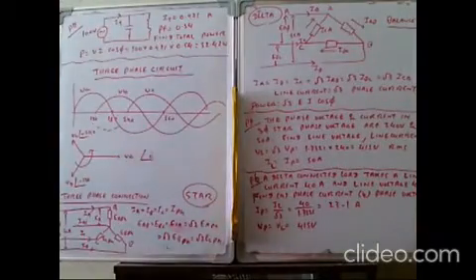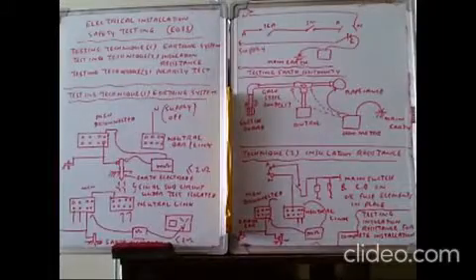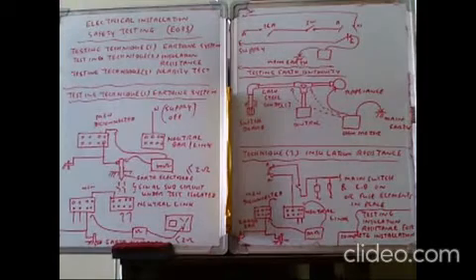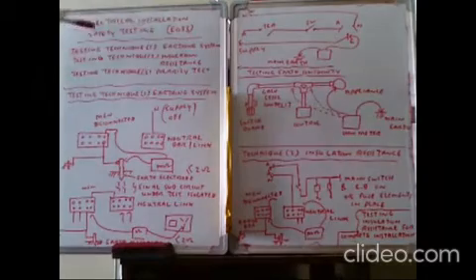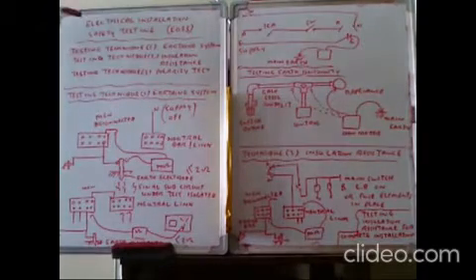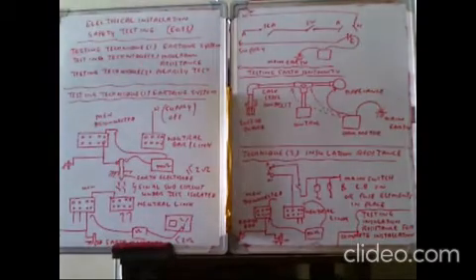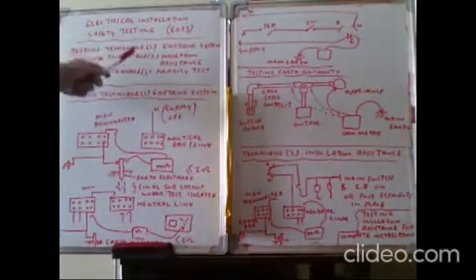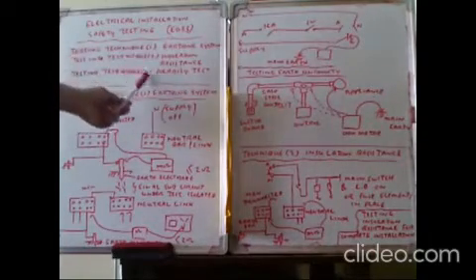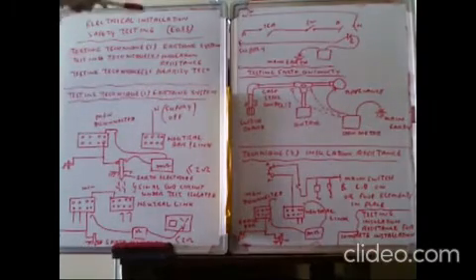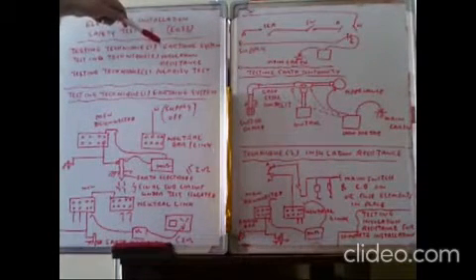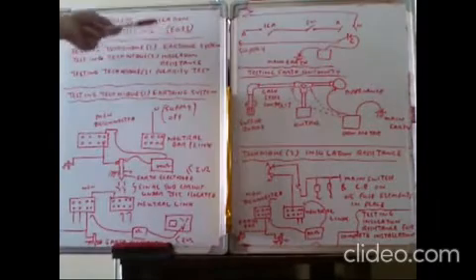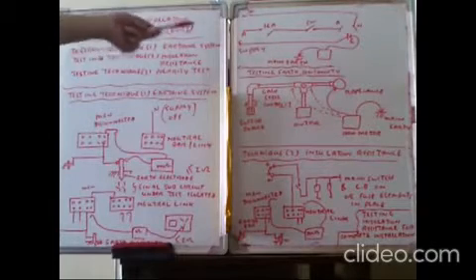After completing electrical wiring for a new building, we must test the electrical installation safety. There are three testing techniques: technique one is the earthing system test, technique two is the insulation resistance test, and technique three is the polarity test. The earthing system protects against electric shock when a fault occurs on metal parts.